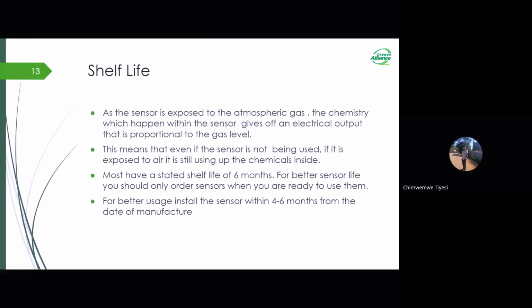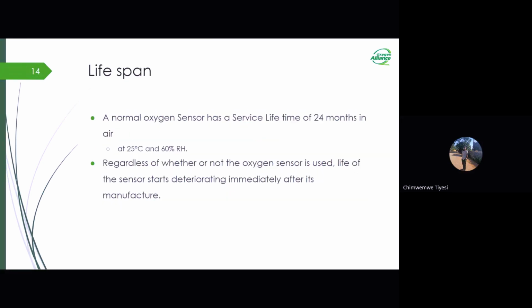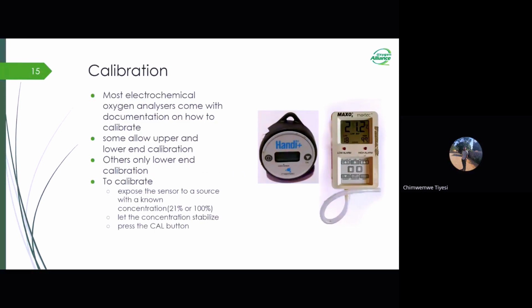Next, I want to talk about the calibration of the electrochemical oxygen analyzer. Most electrochemical oxygen analyzers come with documentation on how you can calibrate. Some of these allow upper end calibration, others only allow lower end calibration, and then you have others that allow both. You can see in the graphics, the one to your left, the black and blue, only allows calibration on the lower end, while the other you can calibrate on the upper and lower end.